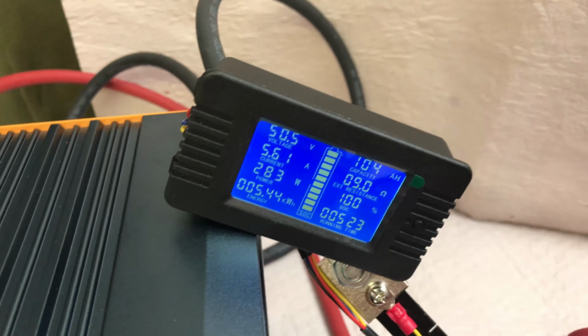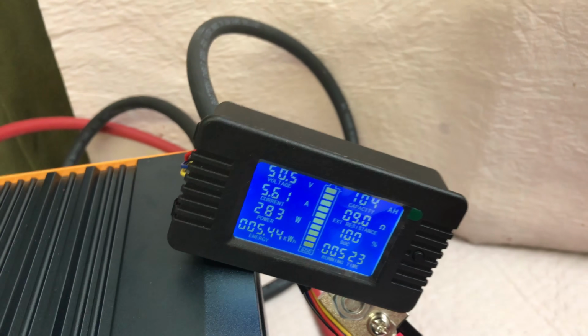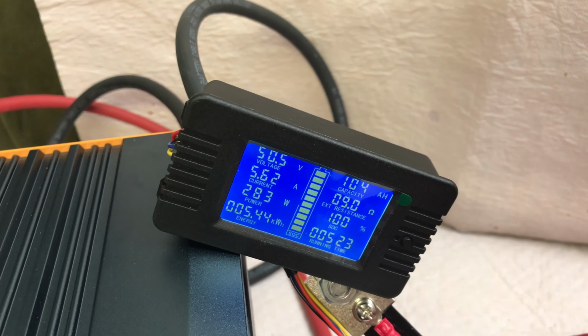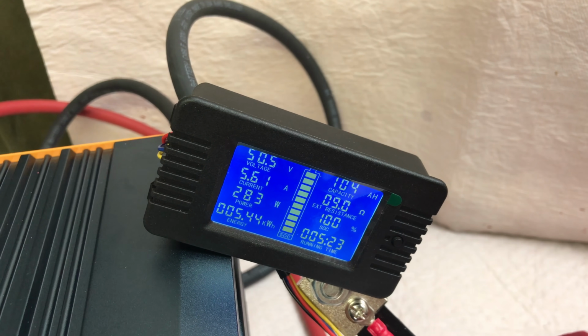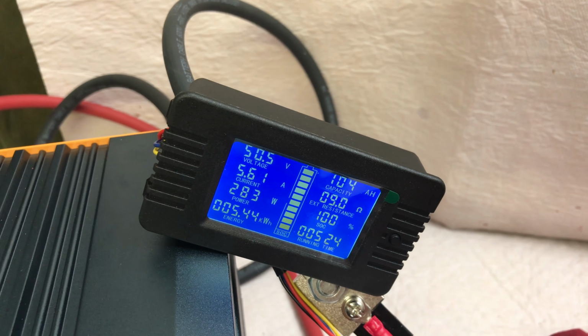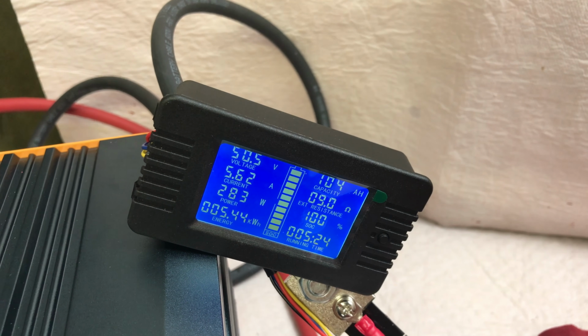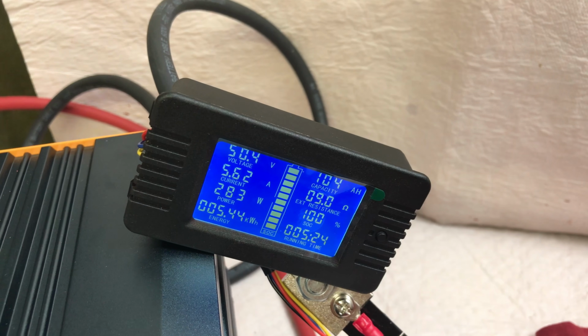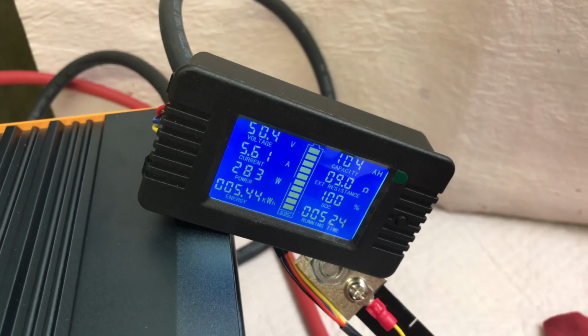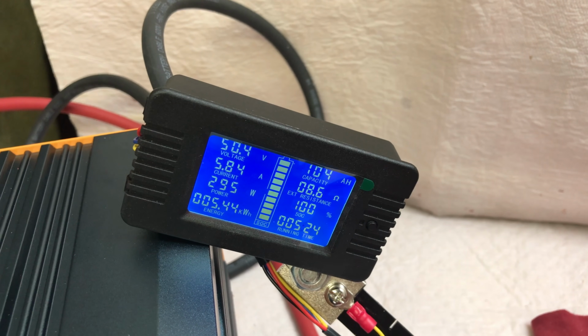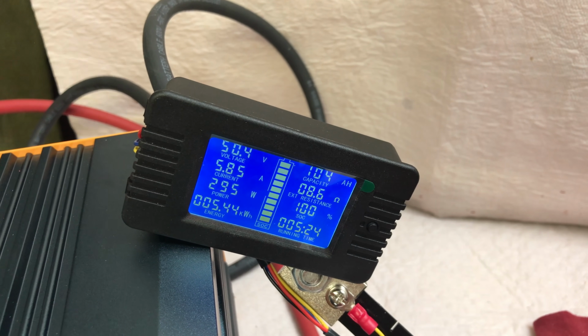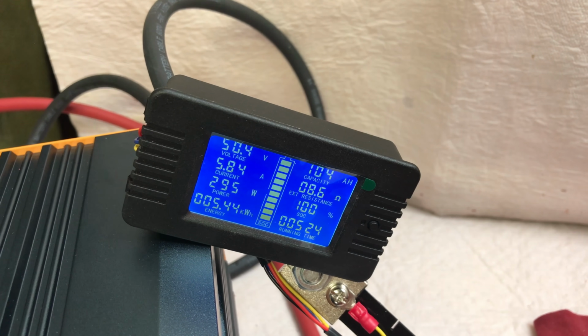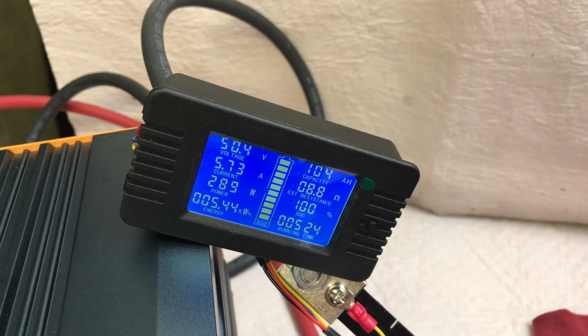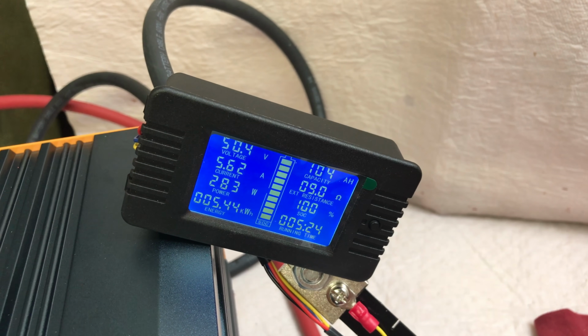Let's look at the meter here. I've got it connected to my 4,000 watt pure sine wave inverter, just running lights and fans and AC for a short period of time. So the total energy was 5,376 watt hours. We've already exceeded that - we're at 5.44 kilowatt hours, or 5,440 watt hours. And you can see in the upper right hand corner 104 amp hours. So when that clicks over to 105, we've met the rated capacity. Don't pay any attention to the percentage on this meter - it's not calibrated to a 48 volt battery, so the percentage is not correct. But all of the other information is accurate.